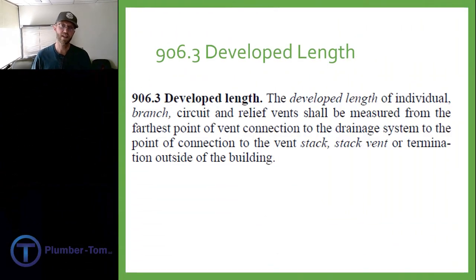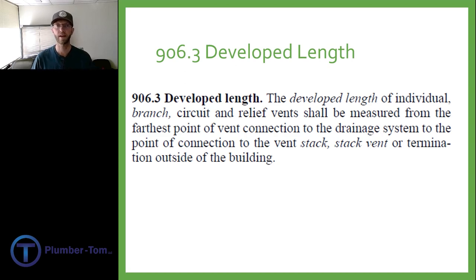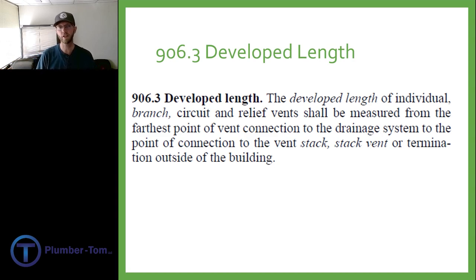Let's focus on the definition of developed length. Section 906.3 says the developed length of an individual branch circuit and relief vents shall be measured from the farthest point of the vent connection to the drainage system to the point of connection to the vent stack, stack vent, or termination outside the building. So we can measure individual vents from the point where they connect to a drain to wherever they terminate — that termination could be a stack, a vent stack, or it could go outside.